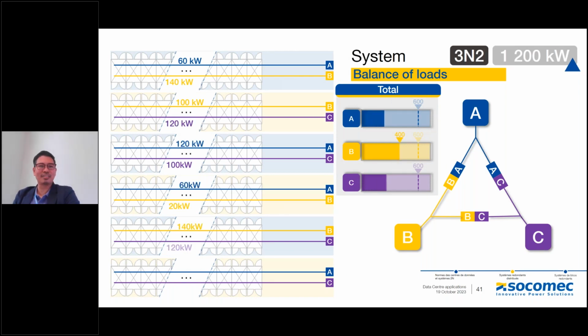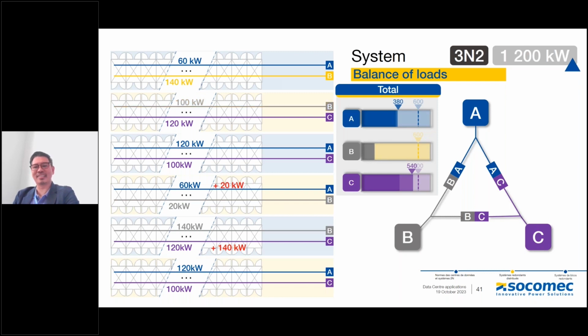As you can see here, the load changes and we cannot dictate where the load will go. When systems reach certain capacities and you go to downgrade mode, there's a possibility of that load moving to the incorrect system. Depending on those systems, it can cause an overload, especially since this all happens dynamically in a data center. When you go into downgrade mode, or one leg is disconnected or on maintenance, you have the possibility of overloading a system, and this can create a chain reaction to the whole design.